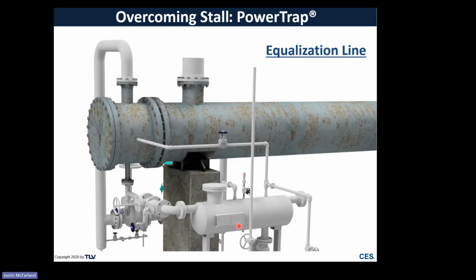If there's a scenario where, let's say, either of these begin to creep up in pressure because there's a restriction in the line or a blockage, or it's tied to an incorrect location, well then basically we can get to a scenario where this begins to pressurize, and now we're back to a negative differential scenario where we have a lower pressure here and a higher pressure here. Condensate cannot gravity drain, and this system either may malfunction or has a reduction in capacity, all of which are going to cause problems.